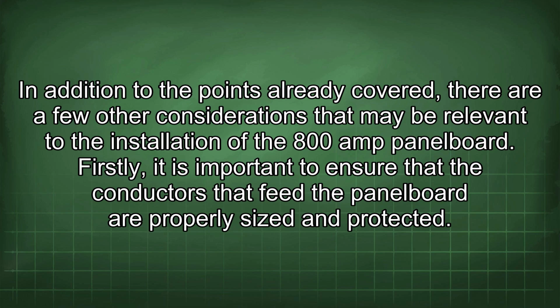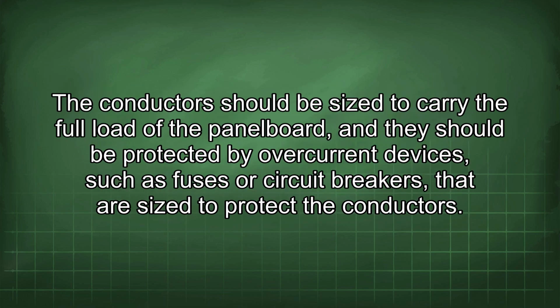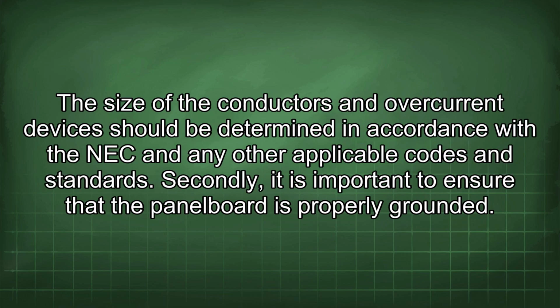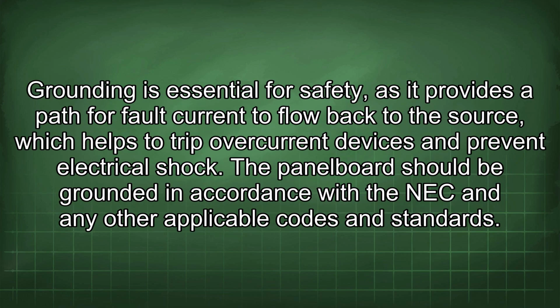Firstly, it is important to ensure that the conductors that feed the panel board are properly sized and protected. The conductors should be sized to carry the full load of the panel board, and they should be protected by overcurrent devices such as fuses or circuit breakers that are sized to protect the conductors. The size of the conductors and overcurrent devices should be determined in accordance with the NEC and any other applicable codes and standards. Secondly, it is important to ensure that the panel board is properly grounded. Grounding is essential for safety, as it provides a path for fault current to flow back to the source, which helps to trip overcurrent devices and prevent electrical shock. The panel board should be grounded in accordance with the NEC and any other applicable codes and standards.